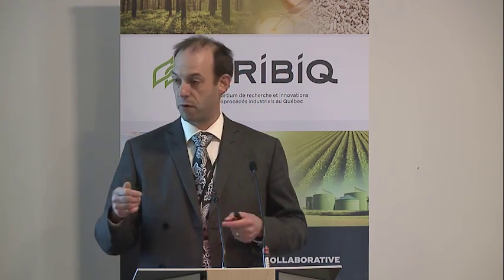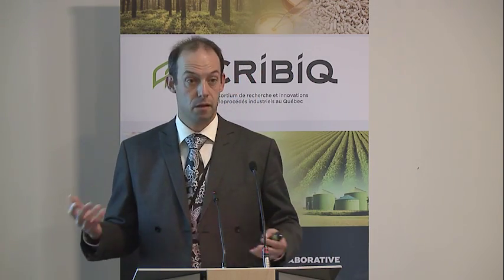Now, what's a FAT test, or factory acceptance test? It's a mechanical and automation test at the factory prior to shipping. You want to buy something, you give a specification and a contract to a manufacturer, and prior to shipping to your plant, you want to make sure that the equipment you bought is correct according to your specification. So you can go to the site, prepare some tests with the supplier, and assist in these tests to make sure that all the specifications for the automation and for the mechanical operation are correct.